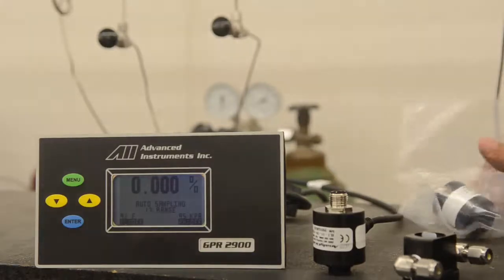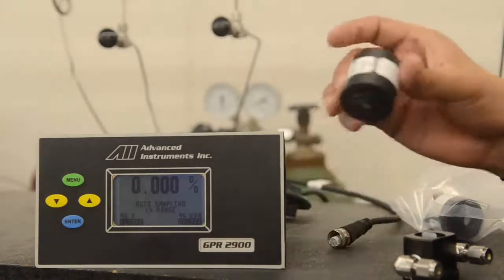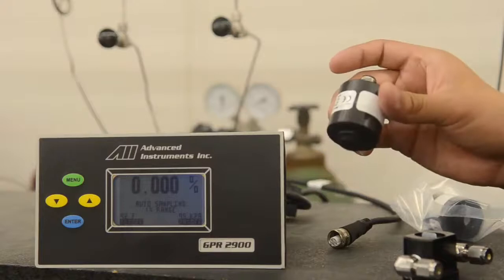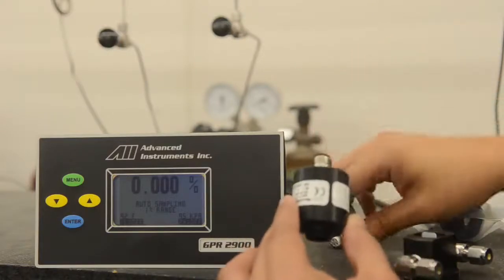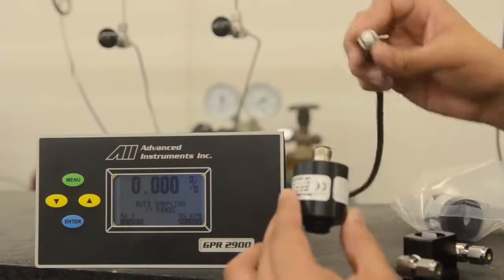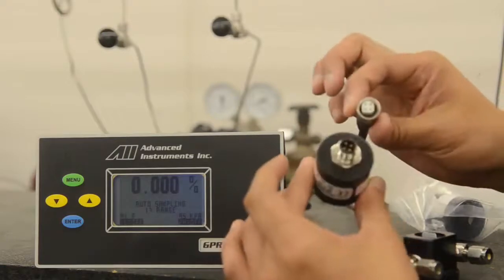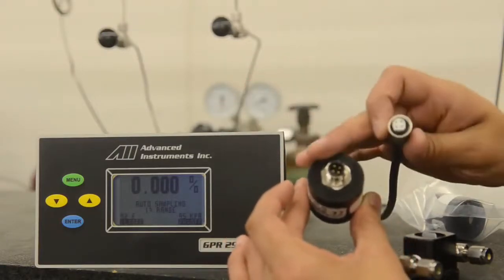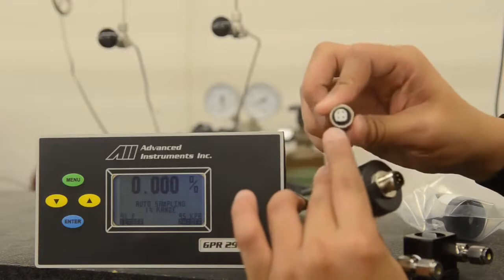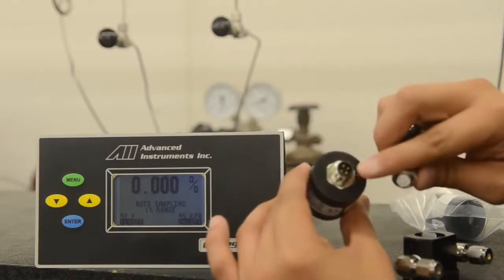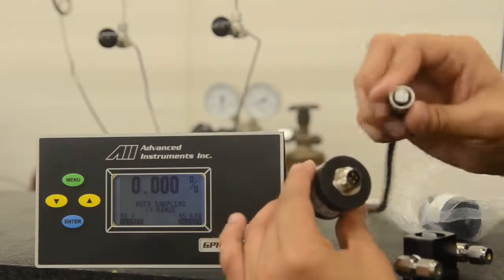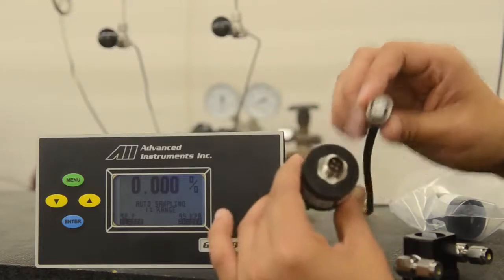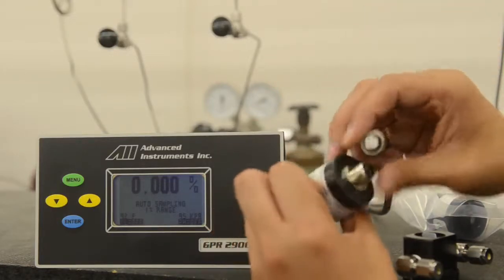Now, when you receive the oxygen sensor, it will be bagged as so. You can open up the bag and remove the sensor, and you'll have the sensor as you see here. Now, make sure all your connections on the back are correct, and make your connection to the sensor from the main module to the oxygen sensor. Now, you'll see there are actually ridges that correspond to the pins to allow you to connect correctly from the sensor to the main module.